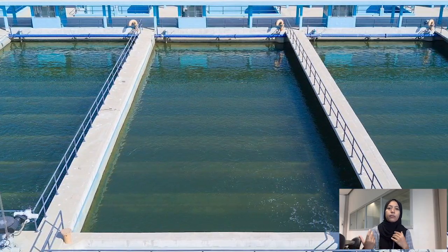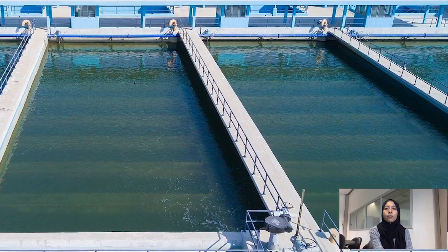The bacteria will digest the contaminant as water passes through the top layer of the sand. The disadvantage of it is it needs several days to re-establish the bacterial community after cleaning the filter. After filter is operated for a while, the sand becomes clogged with particles and must be backwashed. Flow through the filter is reversed and the sand and particles are suspended. The particles are lighter than the sand, so they rise and flush from the system. So this is how the filtration process is being used inside the drinking water system.